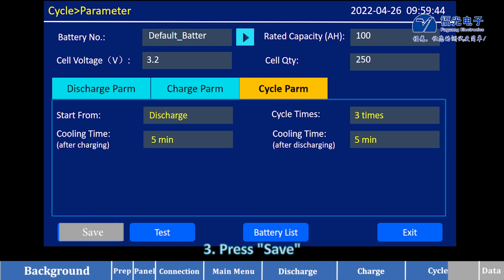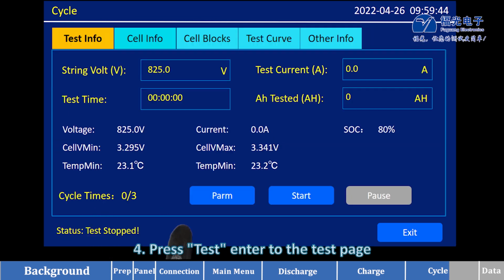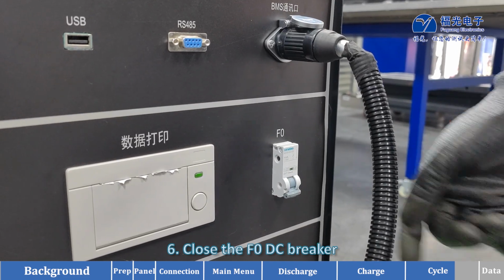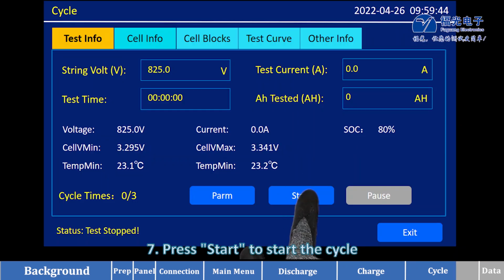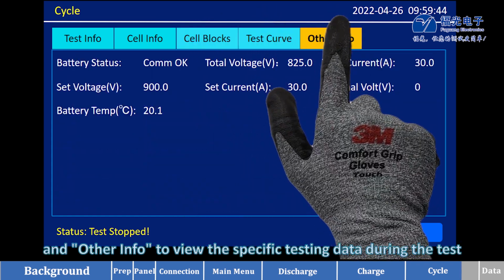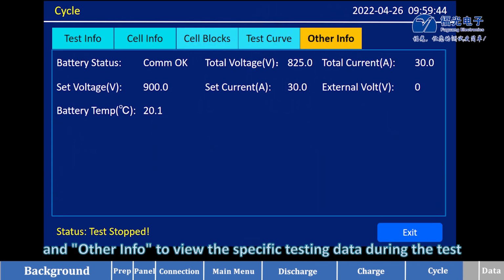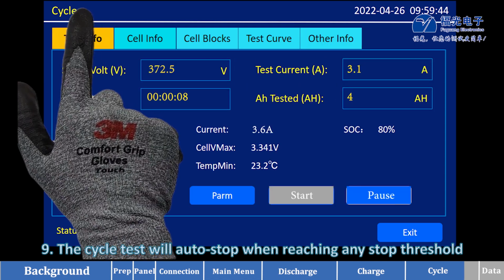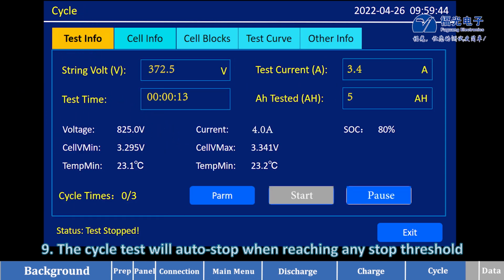Third, press save. Fourth, press test enter to the test page. Fifth, check the data reading by BMS. Sixth, close the F0 DC breaker. Seventh, press start to start the cycle. Eighth, switch cell info, cell blocks, test curve, and other info to view the specific testing data during the test. Ninth, the cycle test will auto-stop when reaching any stop threshold.